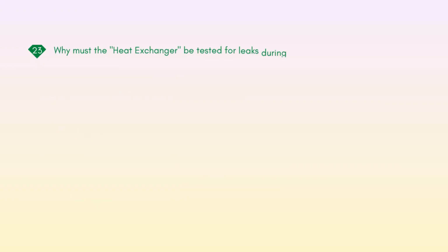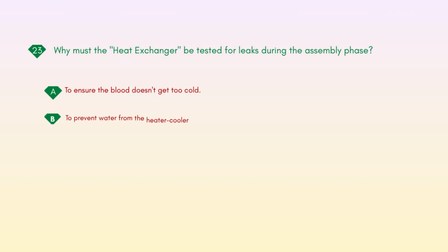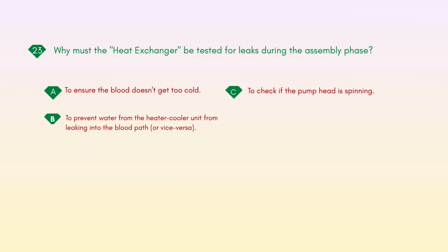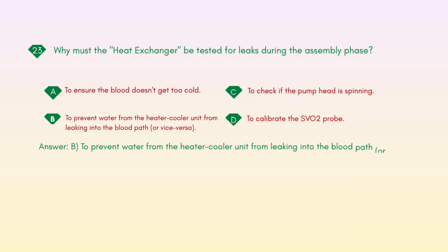Why must the heat exchanger be tested for leaks during the assembly phase? A. To ensure the blood doesn't get too cold. B. To prevent water from the heater-cooler unit from leaking into the blood path, or vice versa. C. To check if the pump head is spinning. D. To calibrate the SVO2 probe. Answer: B. To prevent water from the heater-cooler unit from leaking into the blood path, or vice versa.